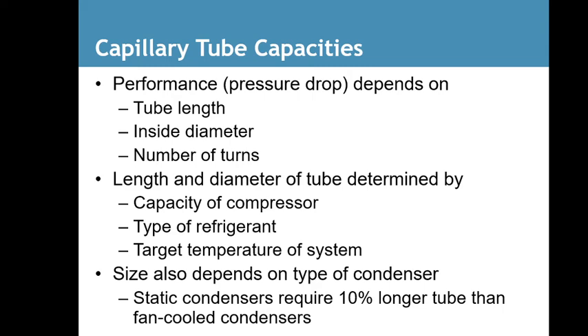Capillary tube capacities. It all depends on the length of the tube, the inside diameter of the tube, and the number of turns. And you're probably thinking, well, if the tube is the same size on the inside when it goes around the turn, why should that matter? Well, like anything, bends take a little bit more work to go around. When you have a 90-degree bend, either on airflow in your ductwork, capillary tubes, or water flow in your home, that item, whether it's air, refrigerant, or water, has to change direction. And it hits that other side of the 90, and it doesn't make a smooth turn. It kind of runs and then pushes.